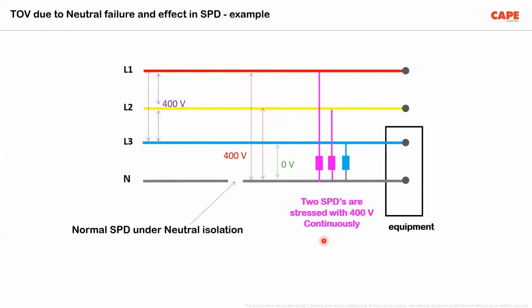These kinds of explosions were happening in a lot of places in India. A lot of failures had happened in the past. So this 400 volt stress on the SPD will create failure and fire in the SPD, which may spread through the panel board, and it can be fatal. So in the IEC standard for SPDs, during 2014, a new modification has come. The SPD and the backup fuse. Backup fuse means every SPD will have some kind of backup protection, maybe a fuse or an MCB. The SPD and the backup fuse will be tested with a TOV, and we can expect three results.